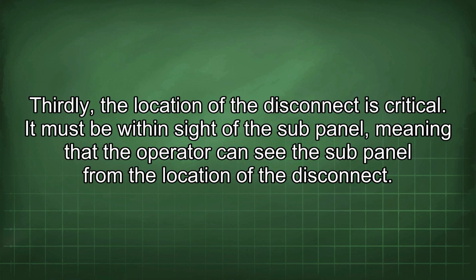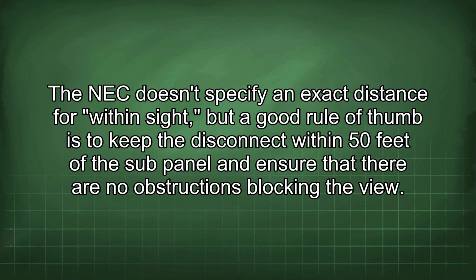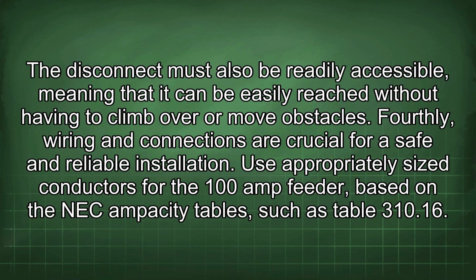Thirdly, the location of the disconnect is critical. It must be within sight of the sub-panel, meaning that the operator can see the sub-panel from the location of the disconnect. The NEC doesn't specify an exact distance for within sight, but a good rule of thumb is to keep the disconnect within 50 feet of the sub-panel and ensure that there are no obstructions blocking the view. The disconnect must also be readily accessible, meaning that it can be easily reached without having to climb over or move obstacles.